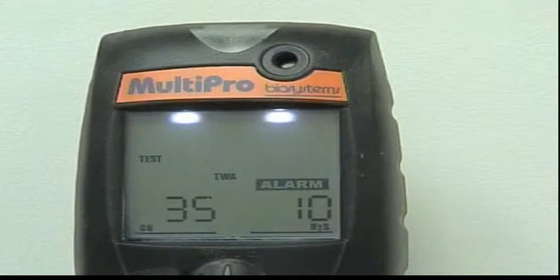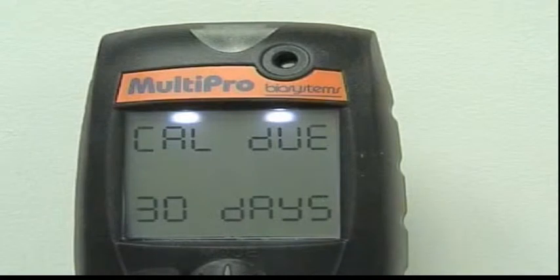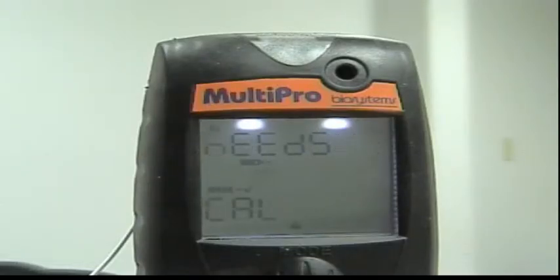Time-weighted average, or TWA values, are calculated by taking the sum of exposure to a particular toxic gas in the current operating session in terms of parts per million hours, and dividing by an 8-hour period. The default TWA alarm for the MultiPro's CO sensor is 35 parts per million. The default TWA value for hydrogen sulfide is 10 parts per million. After the alarm screens have been displayed, the instrument will show when it is due for calibration. If the instrument is past due for calibration, the screen will display Needs Cal. It will not move on to any further screen until the user acknowledges this message by pressing the mode button.